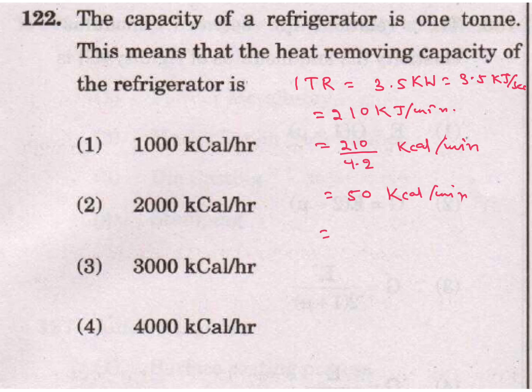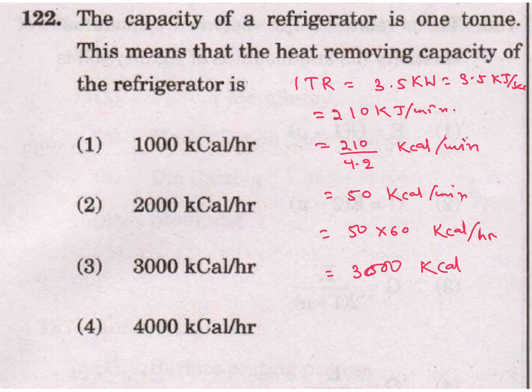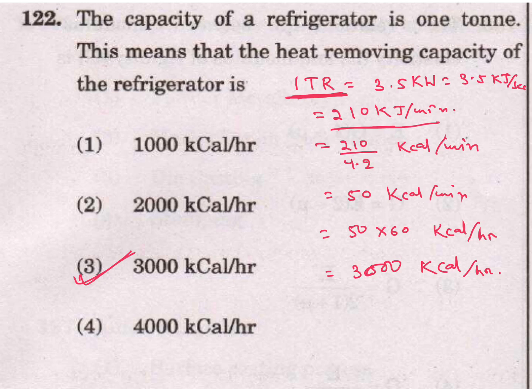Converting to per hour: 50 kcal per minute multiplied by 60 gives 3000 kcal per hour. Many times they ask about 1 ton of refrigeration — you have to convert it into kilo joules per minute, or kilocalories per minute, or kilocalories per hour. All these units are very important to know.